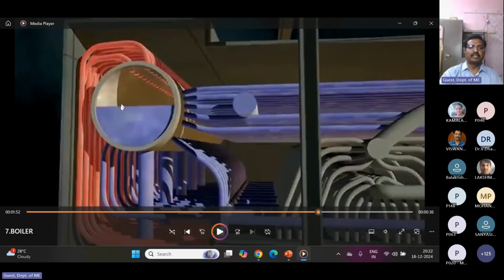Here, if you observe, this is a boiler drum. In the boiler drum, 50% water level is maintained and the other 50% is steam space. Initially, from the boiler feed pump, we supply water through the economizer to the boiler directly. This is the incoming line. After coming here, water fills the boiler drum. These are called downcomers, directly from the bottom of the boiler drum. Through the downcomers, by gravity, water flows downwards.